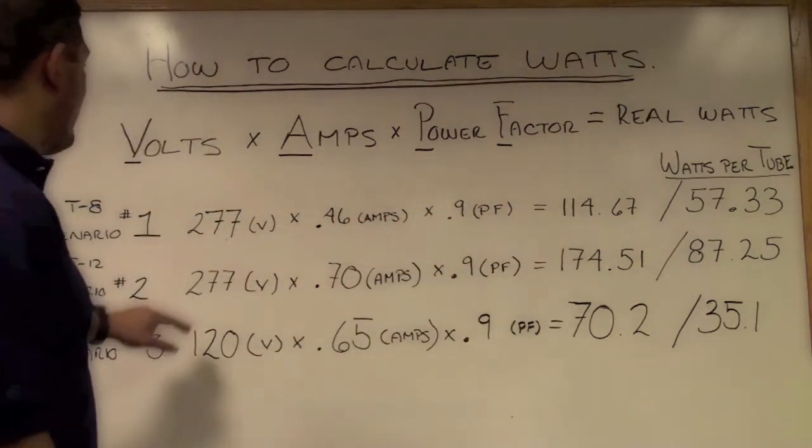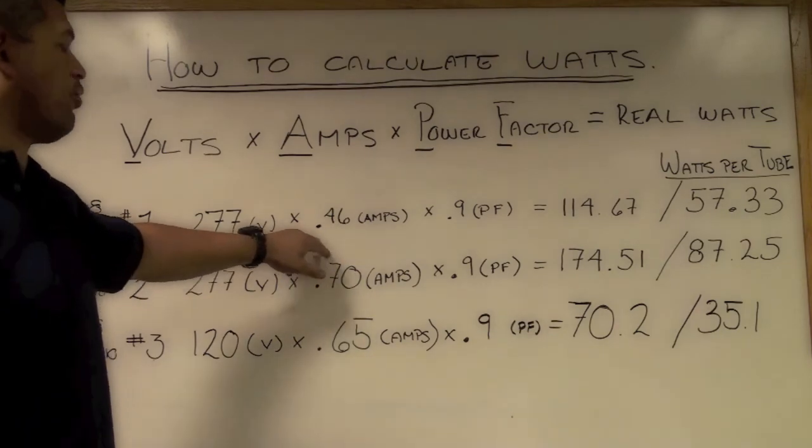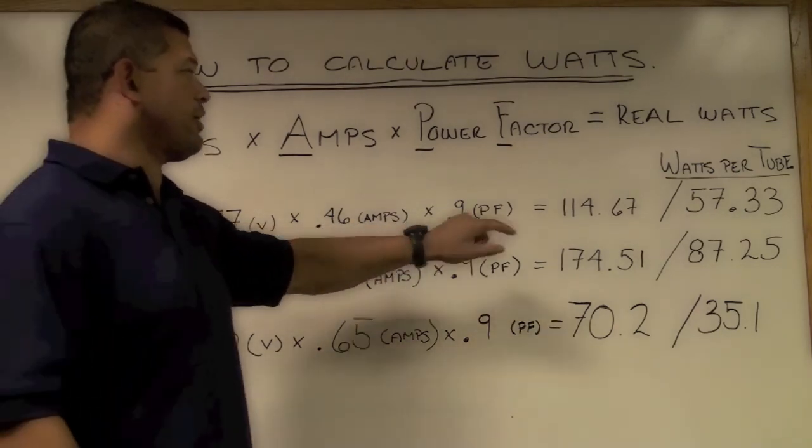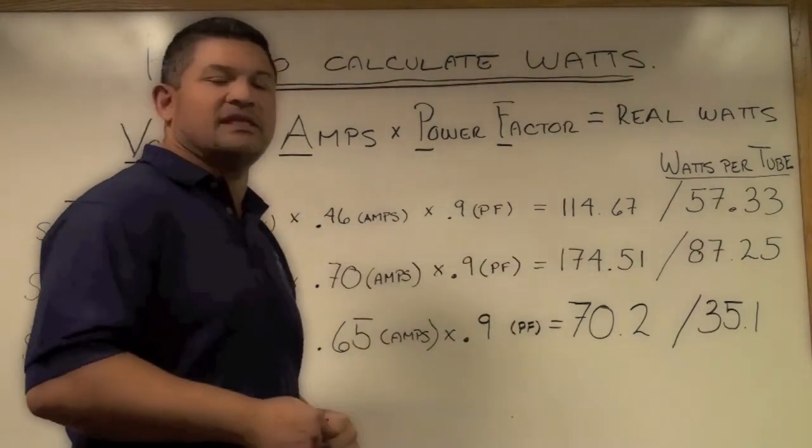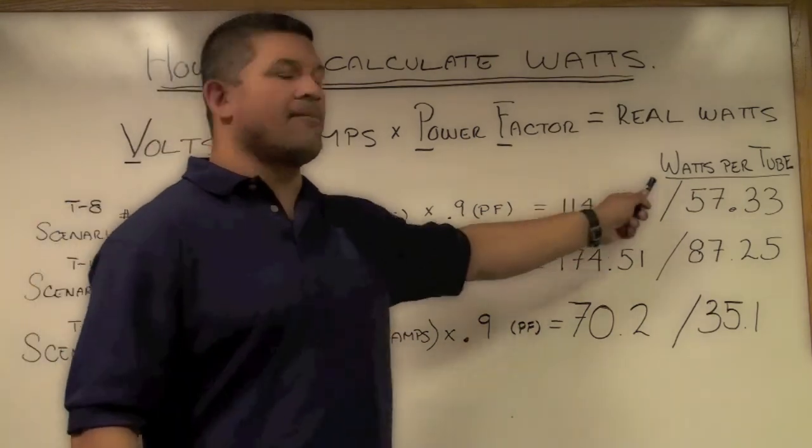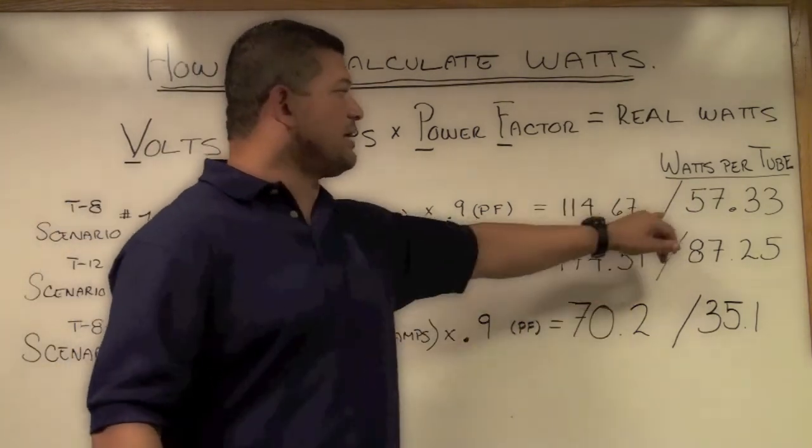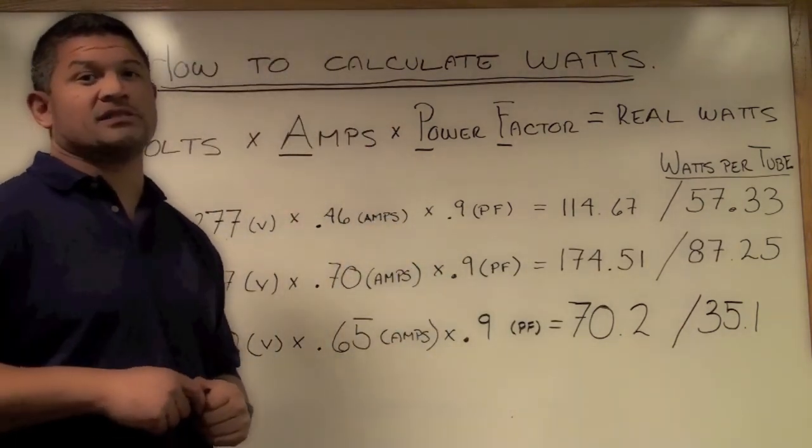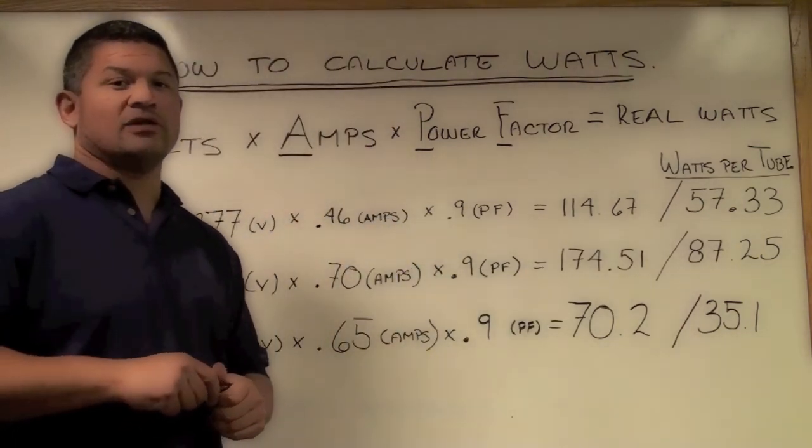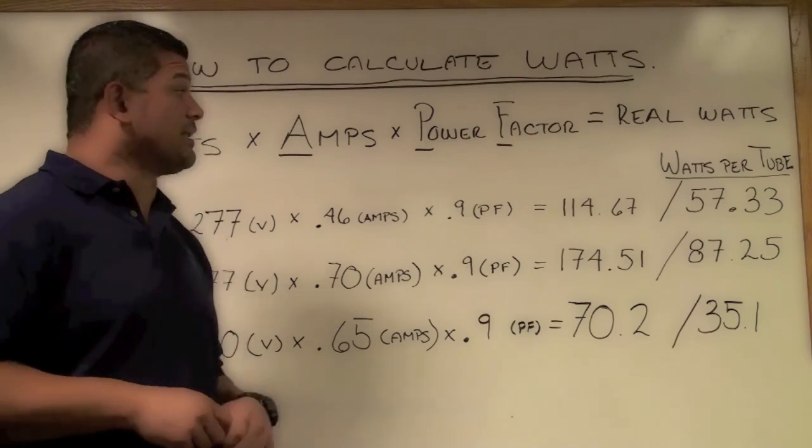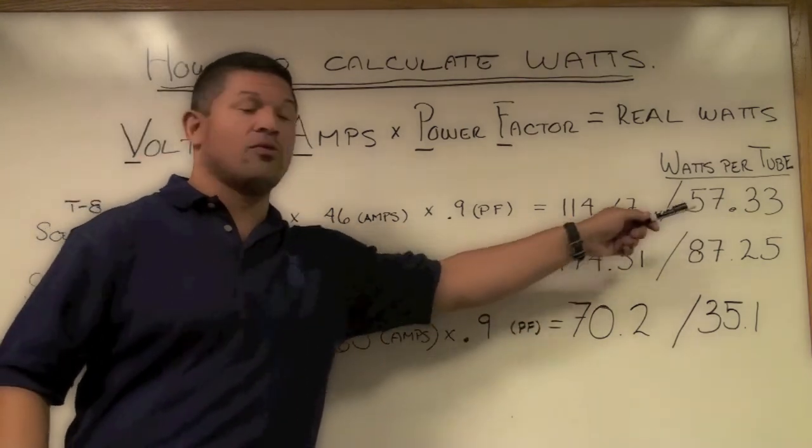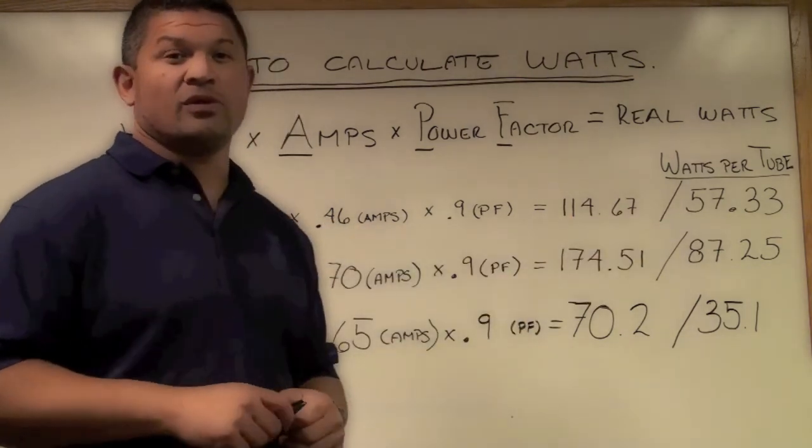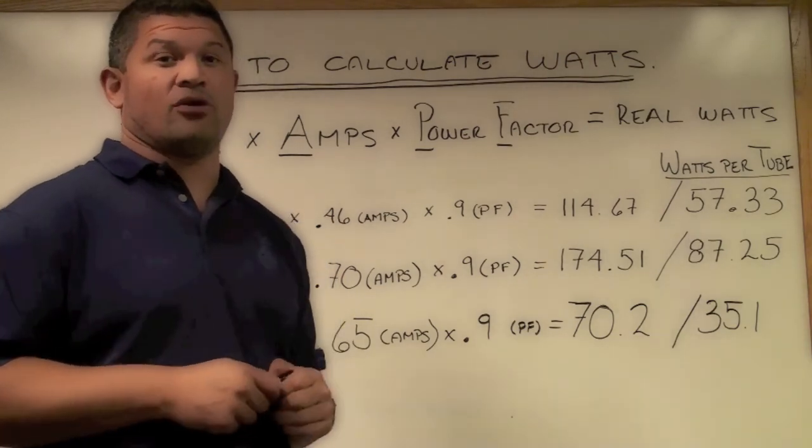In this calculation we have 277 times 0.46 times 0.9 which comes out to 114.67. You divide that by the number of lamps which comes out to 57.33. Those are the total watts consumed and we're looking at retrofitting our location to basically having a solution with LED lights retrofit which would be only 30 watts per lamp.